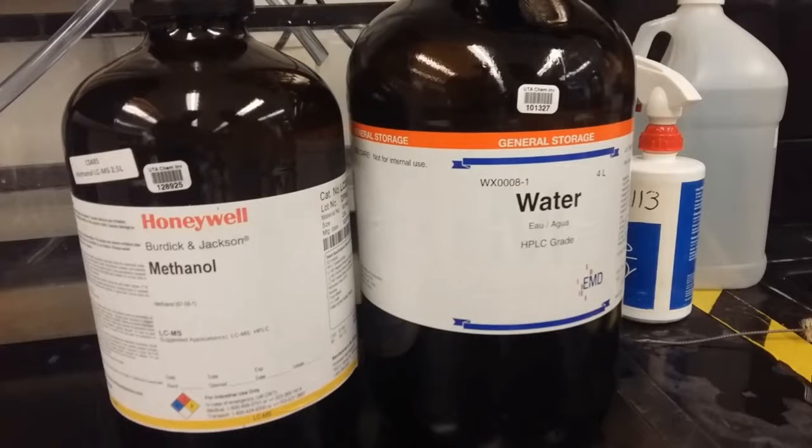Continuing, the initial mobile phase composition of 50-50 methanol water, a hold at that composition for 1 minute and increase to 90-10 methanol water in 6 minutes, and a 1 minute hold at the final composition. Inject the 50 ppm mixture and record the chromatogram, modify the solvent gradient to create the method for the baseline separation.